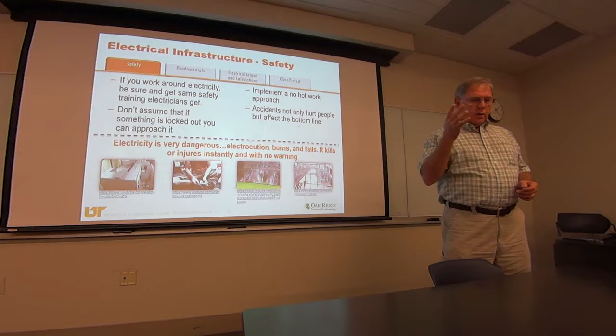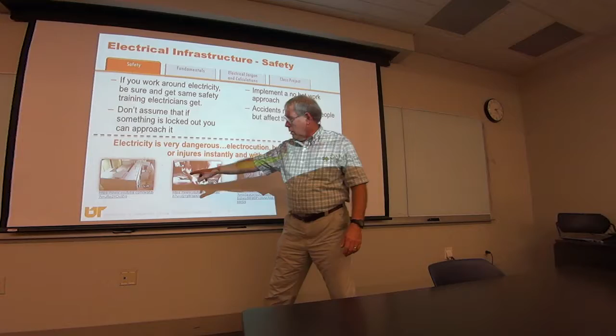If you're in a data center, or in the government, at a laboratory, some guys, you'll see this right here, this happened to those guys, and as a result the lab manager got fired, and DOE came down on all the labs and said no more hot work. By hot work I mean you pull the cover off a live panel, take a screwdriver in there, and start touching energized stuff, turning screws and taking breakers out. People used to do that all the time. And they were doing it.